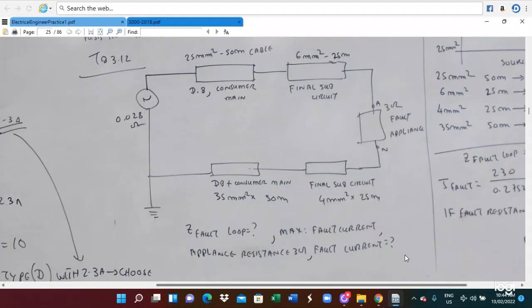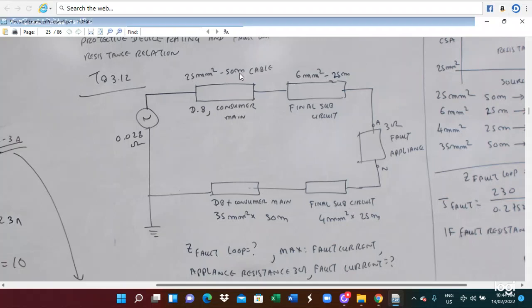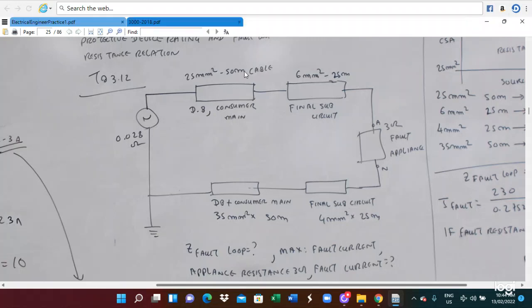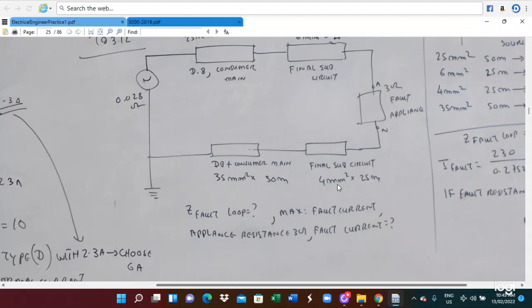Now this problem is given. The supply system is 0.028 ohm, and then the distribution board of the consumer mains has a cable of 25 millimeter square cross-sectional area and 50 meters long. The final circuit is 6 millimeter square cross-sectional area and 25 meters long. The appliance impedance is 3 ohm. Another final circuit has a cable size of 4 millimeter square and 25 meters long, and the consumer mains have a cable size of 35 millimeter square and 50 meters long. We have to find the fault loop impedance and the maximum fault current, and with the appliance at 3 ohm, we have to find the fault current. Those things you have to find.